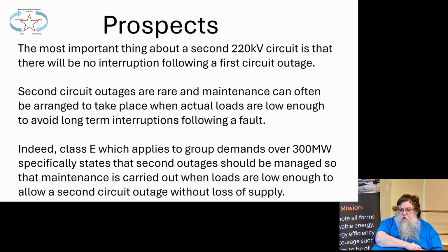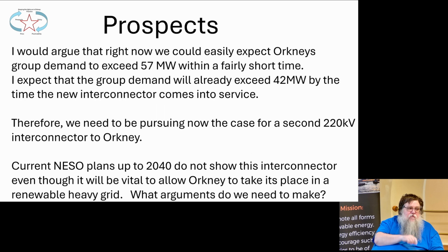Class E, which is above what we actually are interested in, but I've included it because it's quite interesting that it says group demands over 300 megawatts specifically state that second outages should be managed so that maintenance is carried out when loads are low enough to allow a second circuit outage without loss of supply. So even though the standard is 2/3 of group demand have got to stay on, if you manage it so that your first outage is when the load is less than 2/3 of group demand, you can get a fault and not lose any supplies.